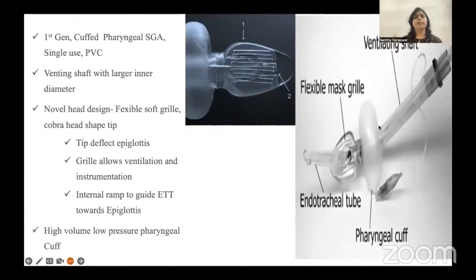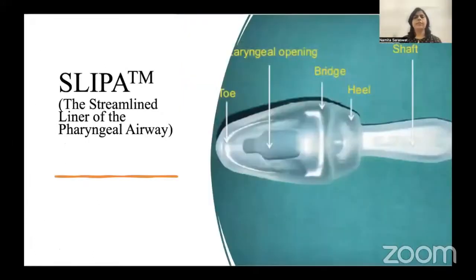The ventilating shaft is wider, has more inner diameter, and you can see this has a novel head design. These are the flexible soft grills, and the tip resembles the cobra head. The function of this tip is that it will deflect the epiglottis, and these soft grills will provide ventilation as well as instrumentation. You can see a round shape over here. These are the internal ramps which will guide the endotracheal tube towards the epiglottis, and the cuff is a high volume, low pressure pharyngeal cuff.